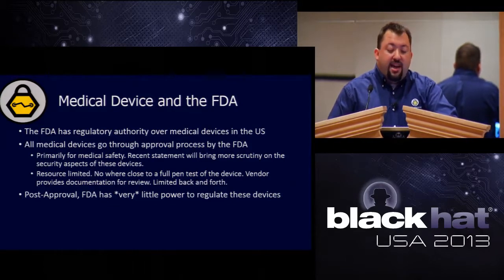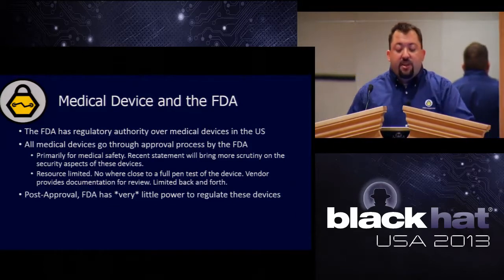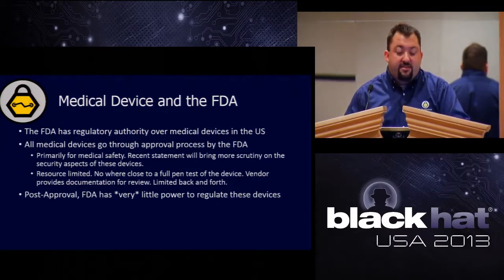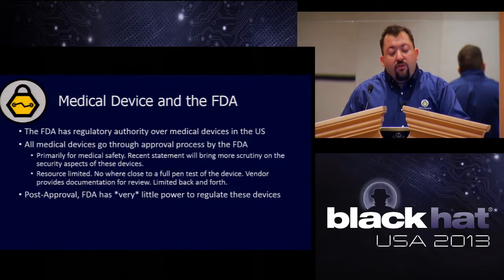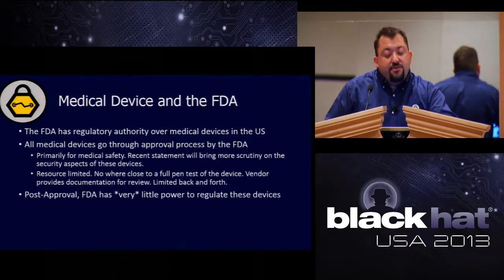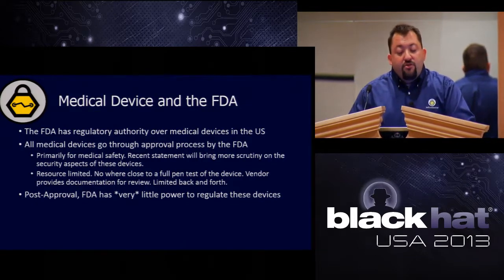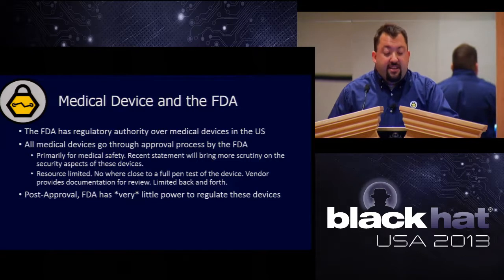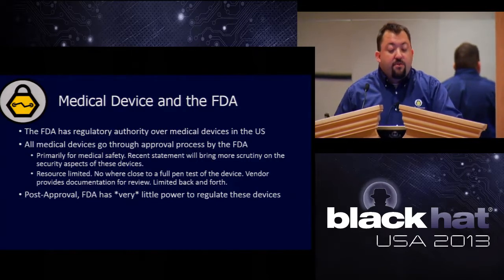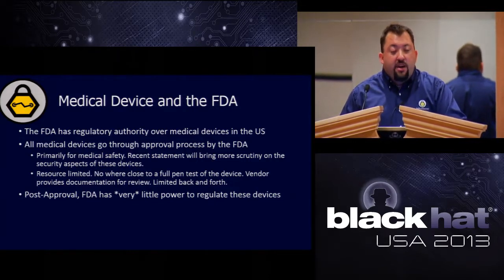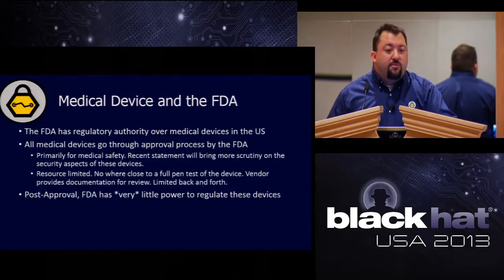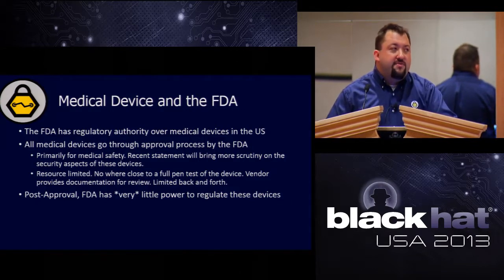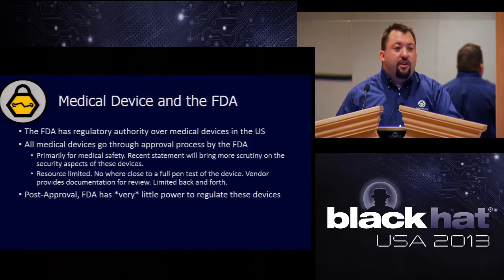Now recently, last month, they came forward and said that there's going to be more scrutiny on the security aspects of these devices. The other thing you need to know about the FDA is their resources are fairly limited. They're nowhere close to being able to do a full pen test of a device. The vendor provides documentation for review, and there's a very limited back and forth between the FDA and the medical device vendor over what kind of security controls are implemented on these devices.